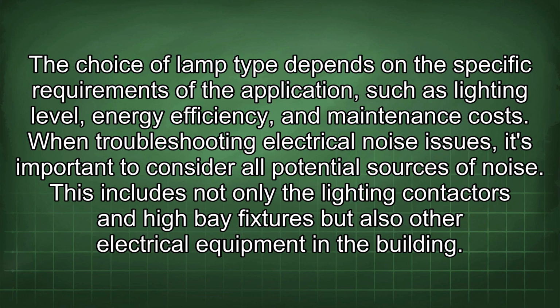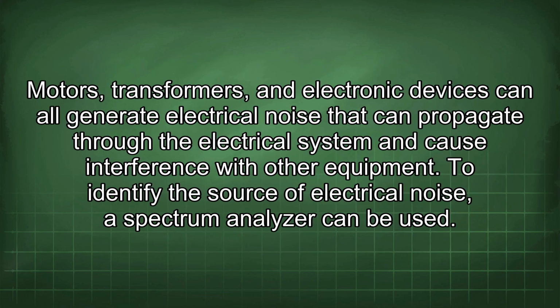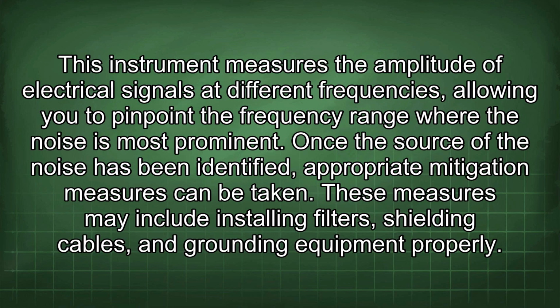When troubleshooting electrical noise issues, it's important to consider all potential sources of noise. This includes not only the lighting contactors and high bay fixtures but also other electrical equipment in the building. Motors, transformers, and electronic devices can all generate electrical noise that can propagate through the electrical system and cause interference with other equipment. To identify the source of electrical noise, a spectrum analyzer can be used. This instrument measures the amplitude of electrical signals at different frequencies, allowing you to pinpoint the frequency range where the noise is most prominent.